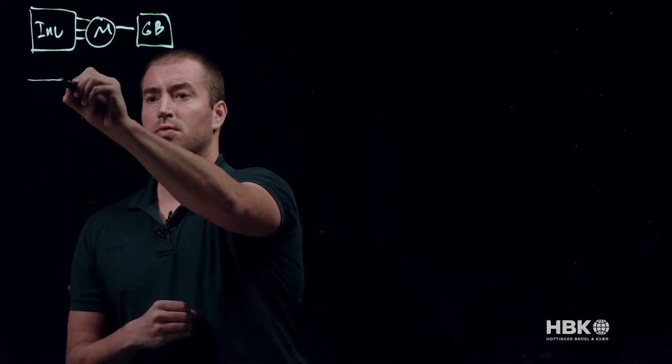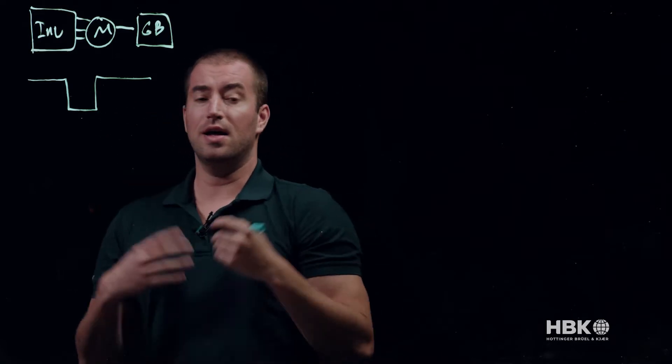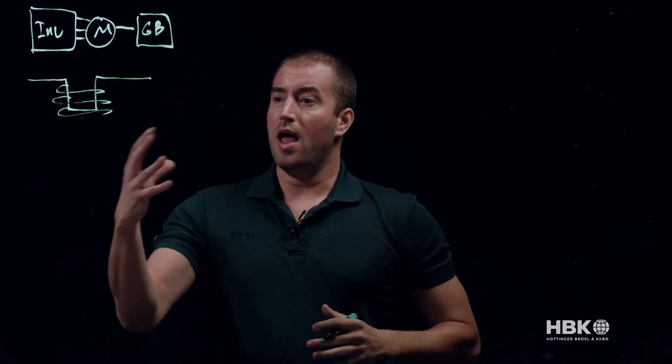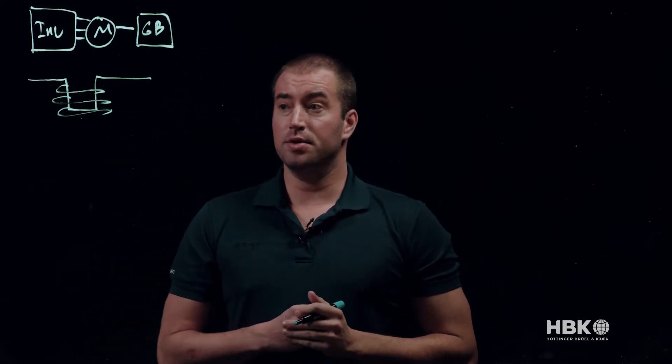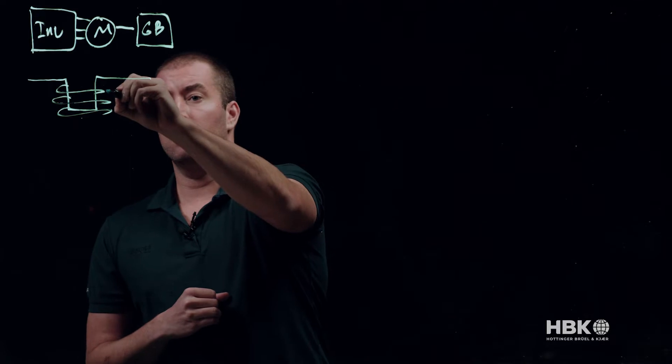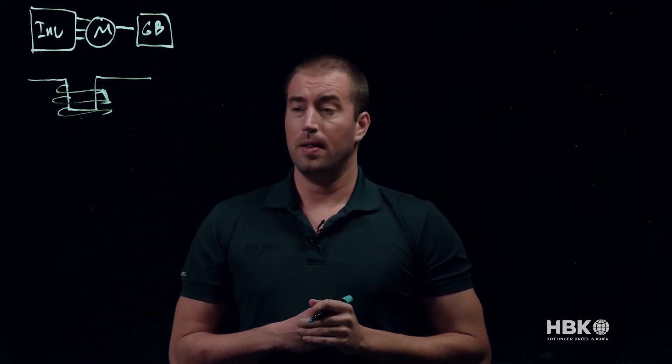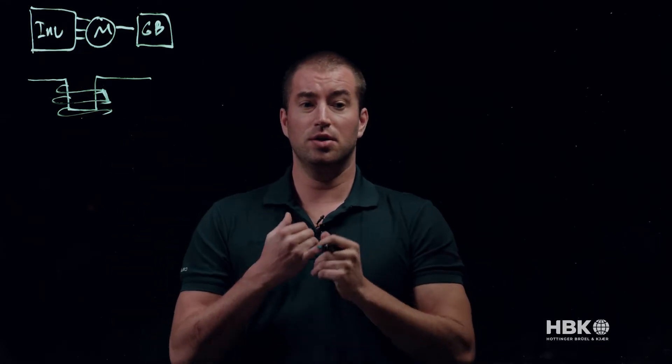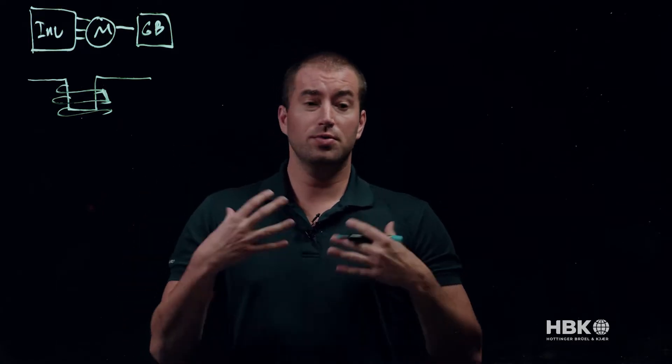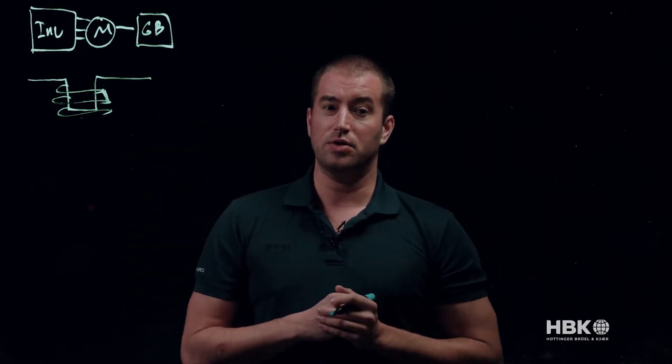So one of the issues with motors is we have a stator that's a chunk of iron, and it has these teeth and these teeth have individual windings around them. If these motor windings are exposed to high temperatures, maybe some vibrations, physical getting hit, these turns of this winding can get shorted together and we call this a turn-to-turn short. This electrically can result in changes of harmonics, increased currents, lowered efficiencies, and also result in more heating or vibrations. So this is one mode of failure where we see mechanical influences affect the electrical outputs.